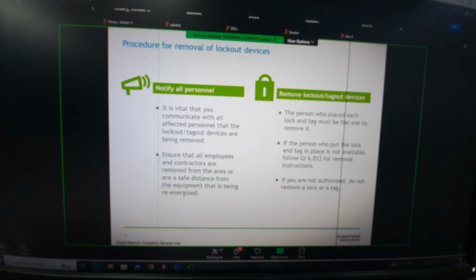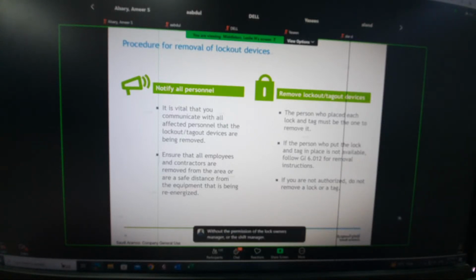Ensure that all employees and contractors are removed from the area before equipment is energized. Lockout tagout devices: the person who places each lock and tag must be the one to remove it. For different operations, this responsibility may be transferred to another supervisor, which should also be documented. If the person who put the lock and tag in place is not available, follow GI 6.012 for removal instructions. Note, no padlock or lockout device shall be cut or forcibly removed without the permission of the lock owner's manager or the shift manager. If you are not authorised, do not remove a lock or a tag.